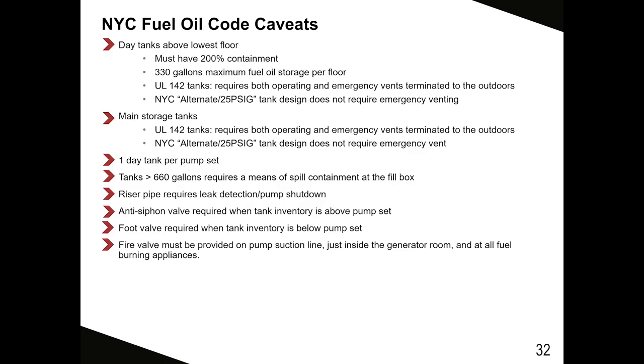Tanks in the basement over 660 gallons require a means of spill containment at the fill box. All basement tanks are in a 2-hour fire rated room minimum. Riser pipe requires leak detection with pump shutdown logic. Anti-siphon valves are used on tanks when the inventory is above the pump inlet. A foot valve is required when the tank inventory is below the pump inlet.